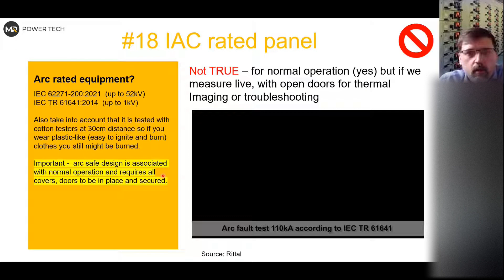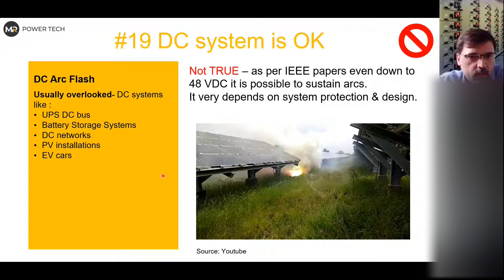And almost at the end, people think DC systems are okay. That's not true, and these systems are very often overlooked when we look at arc flash and also shock hazard. Sometimes they're more than 48 volts, but up to 100 volts DC is considered safe. However, from an arc flash point of view, even down to 48 volts it was proven that we can sustain the arc with quite high incident energy, above 1.2 calories. This applies to PV systems, DC networks, battery storage systems, UPS DC sides and batteries, or EV cars, which now go up to 900 volts DC as far as I've seen.